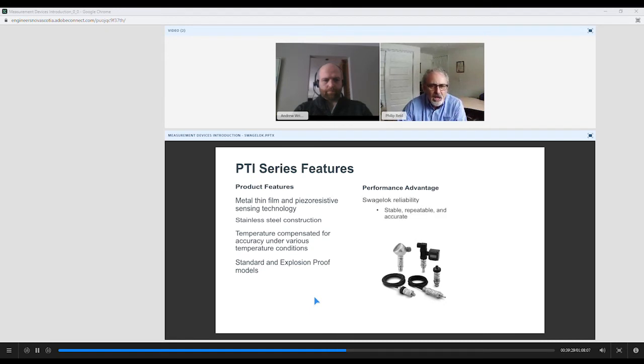where they're going to be used. And again, performance advantages with a transducer, you get stable, repeatable accuracy, very stable over the long run. They're not as susceptible to mechanical damage, and there's a lot of design flexibility. But keep in mind, you will need power at this. It sends a 4 to 20 milliamp output signal. So again, typically instrument signals that you'll have in plants or where you're working. And so these signals will go out, and they're very stable and repeatable, as I mentioned.